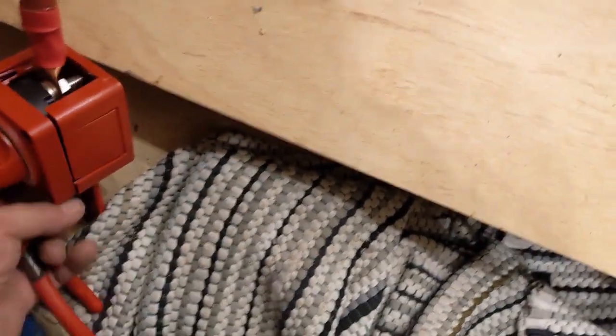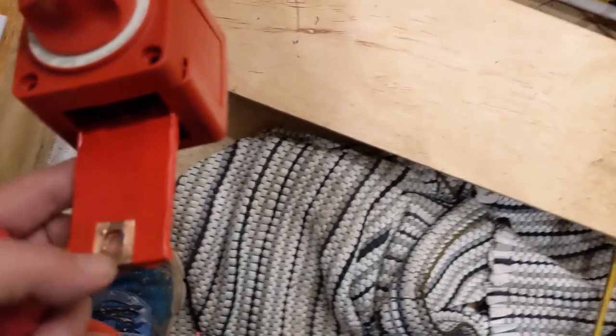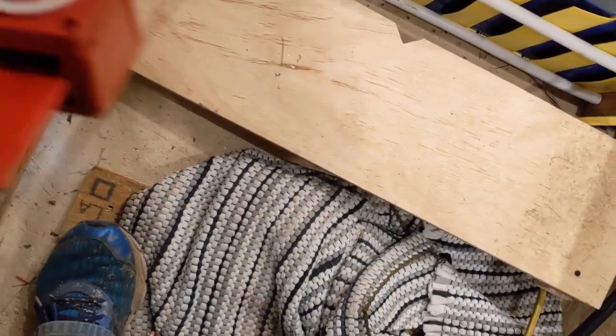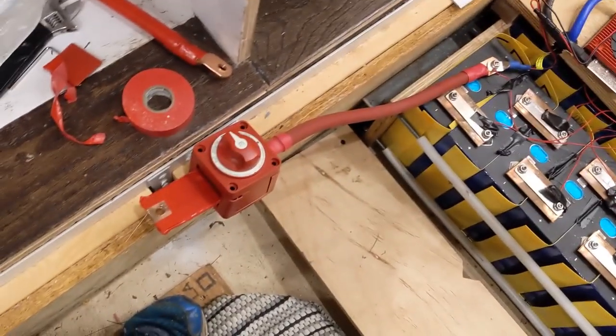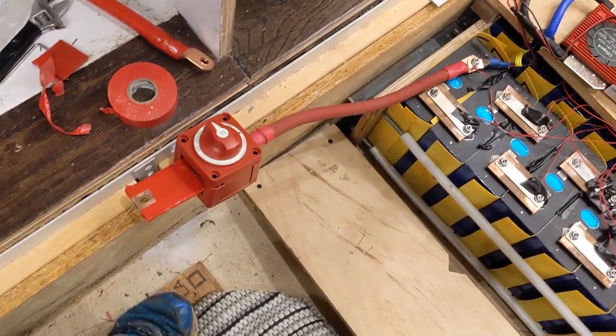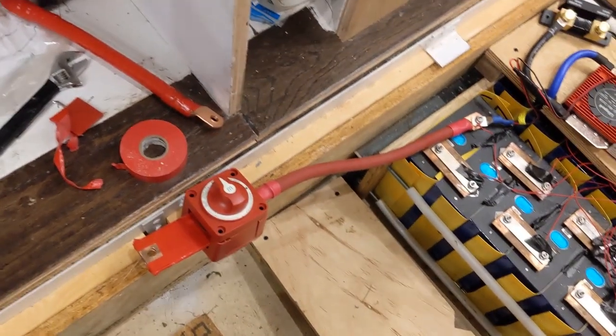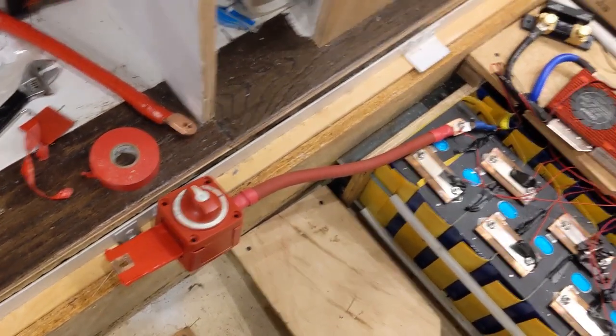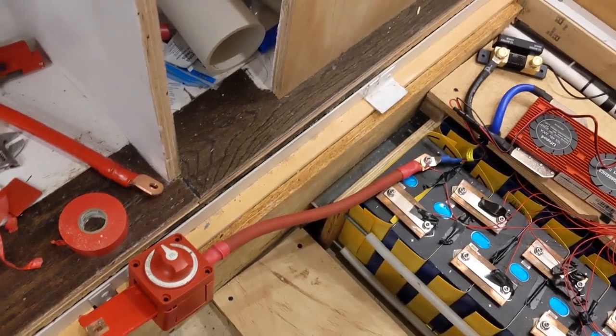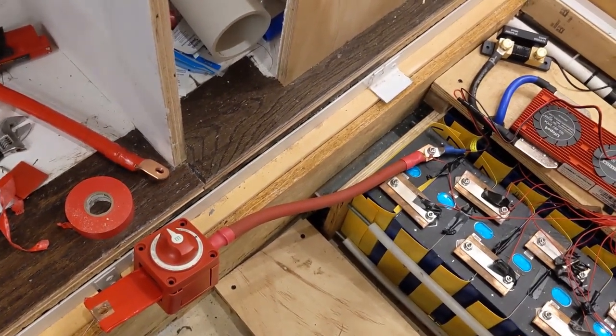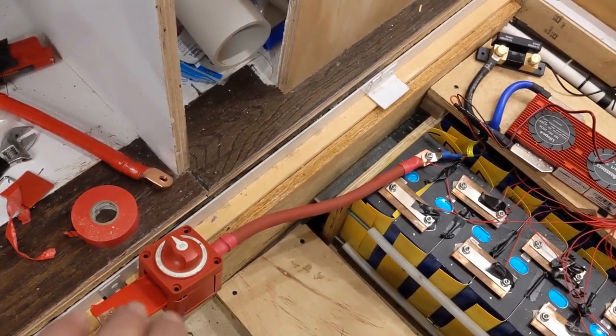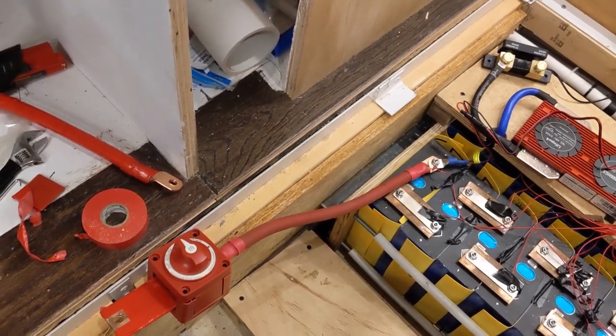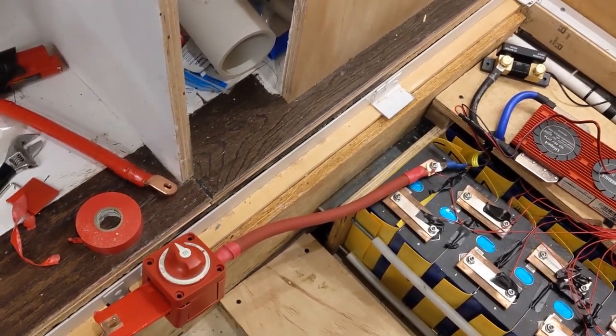I've got a little bit of a bus bar here, double thick copper right here. That is going to connect to the ANL fuse holder, and then from the ANL fuse holder we'll be able to connect the battery, or the inverter DC side. But that's going to go to a bus bar first, actually. So it'll be ANL fuse holder, bus bar, and then the positive terminal block.